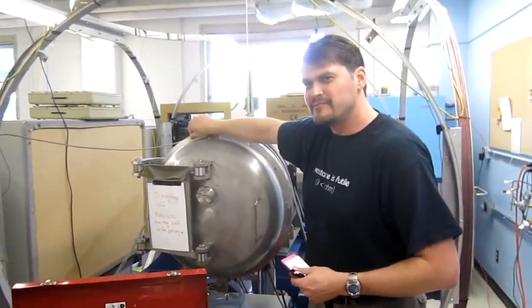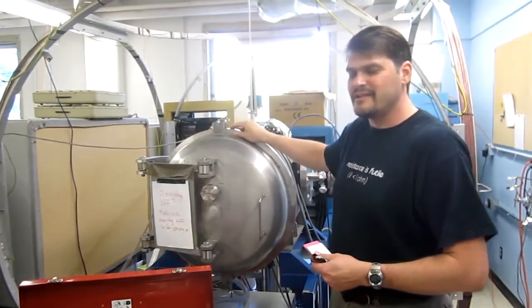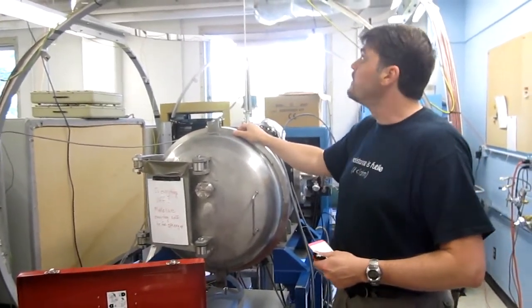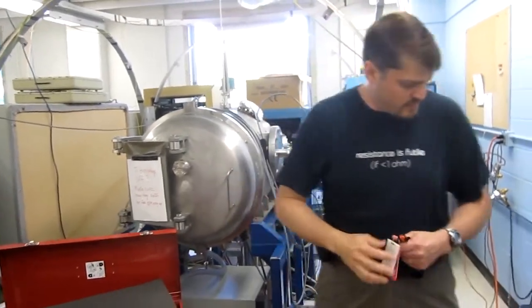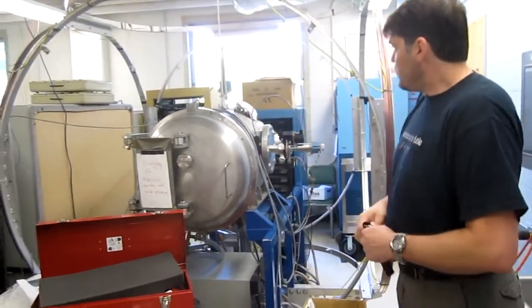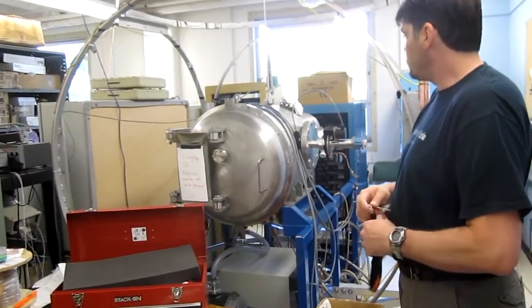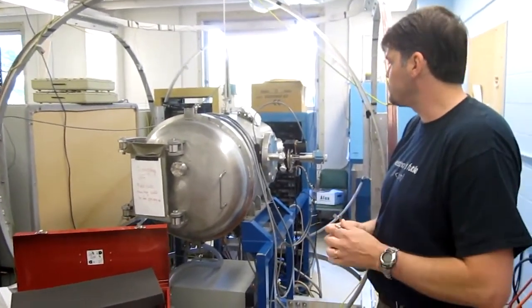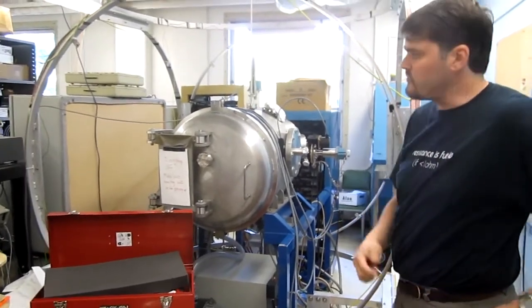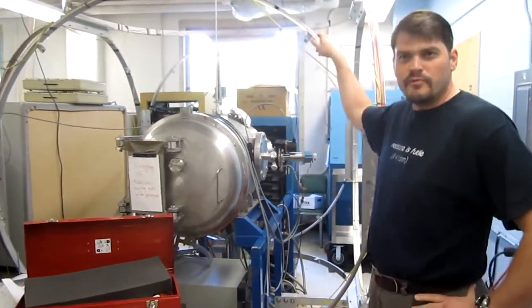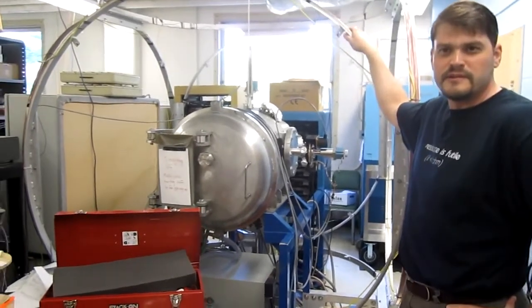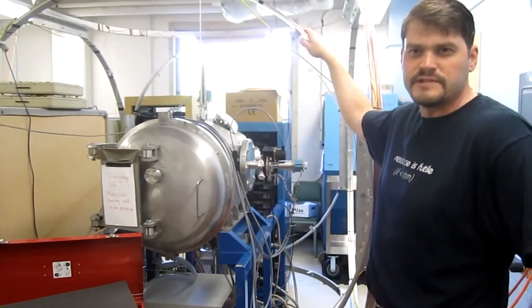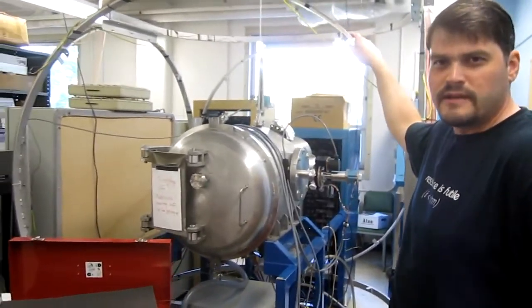But it's not perfectly efficient with this odd shape of the chamber, it wasn't doing a great job. We came across these coils that had been built for another group, an old group that's no longer active at the university. So we got this from their chamber, applied it to ours, and now we drive current through here to essentially null out the Earth's field, which allows us to go to much lower energies, get down below 100 eV to do our calibration.